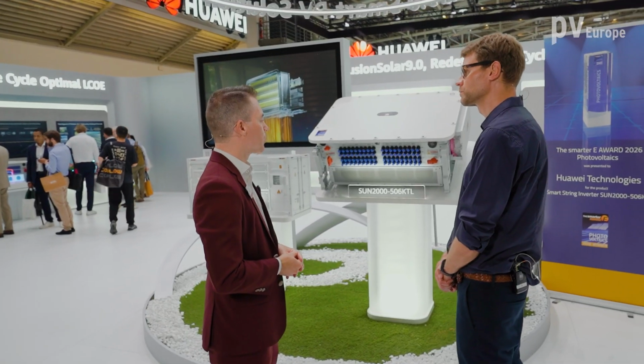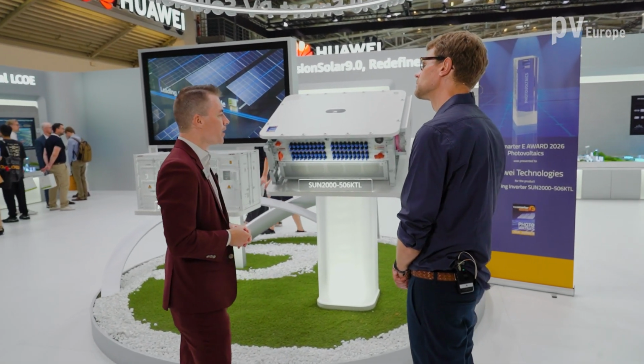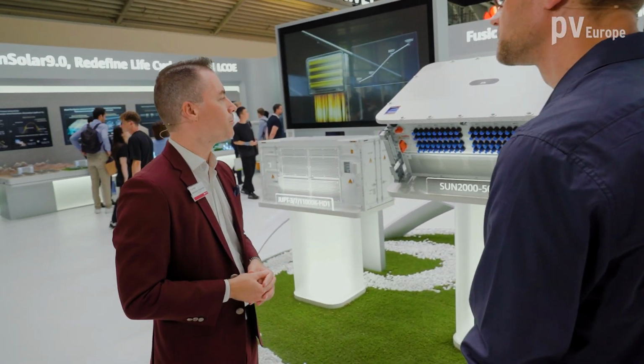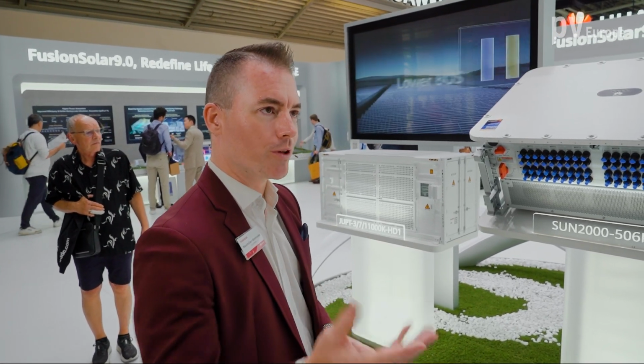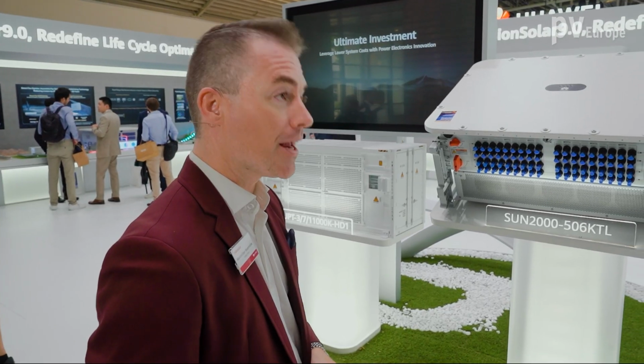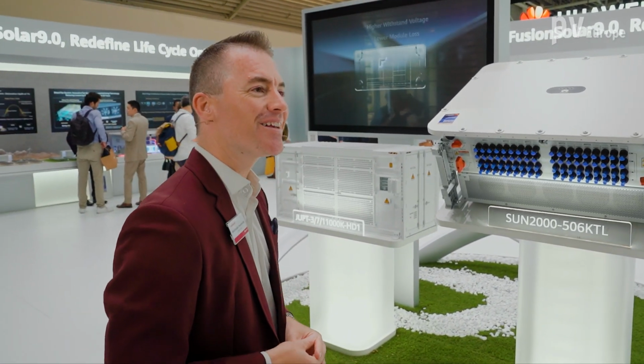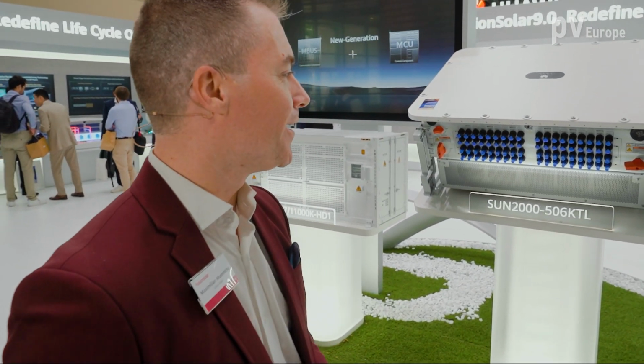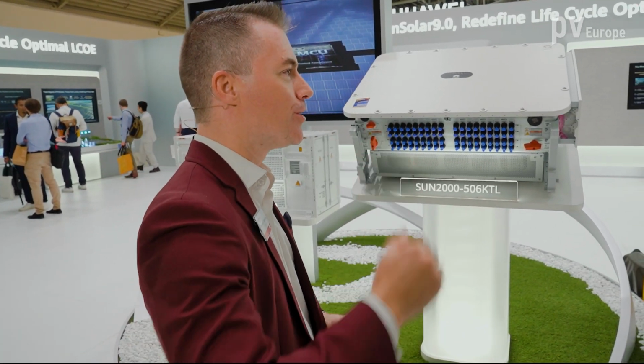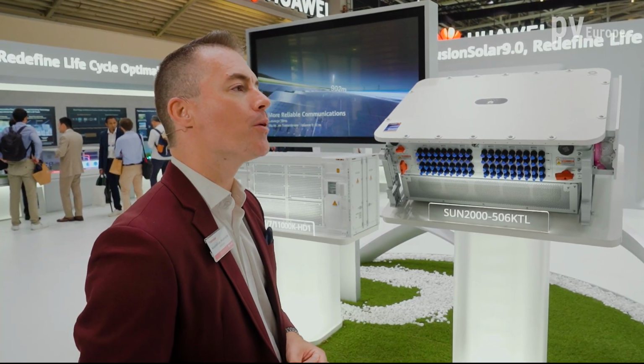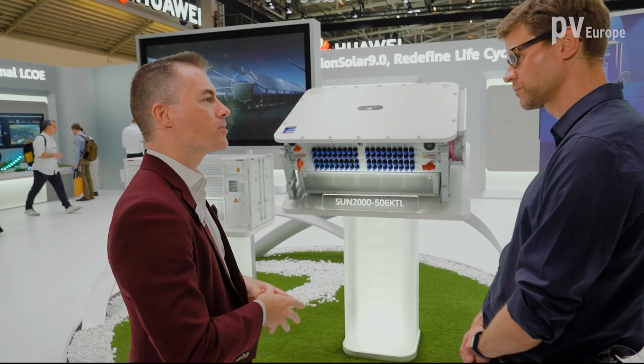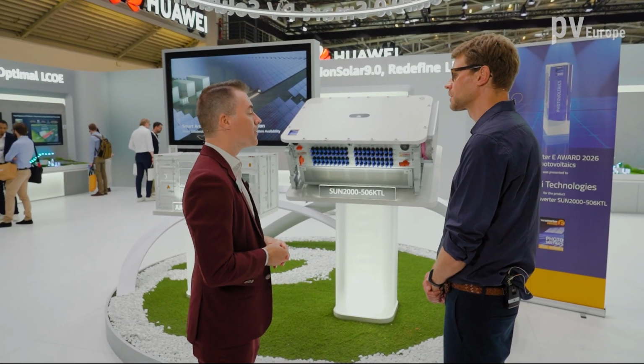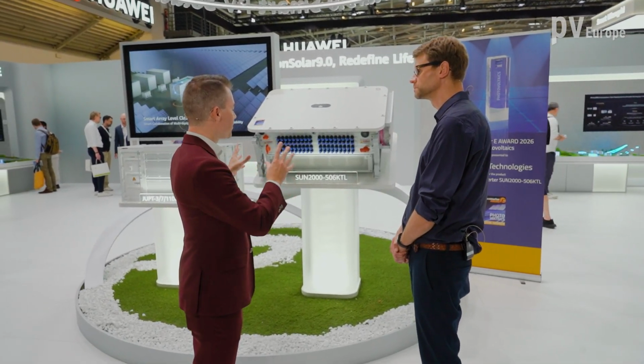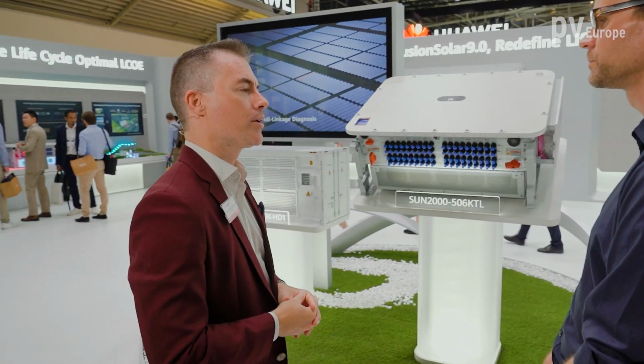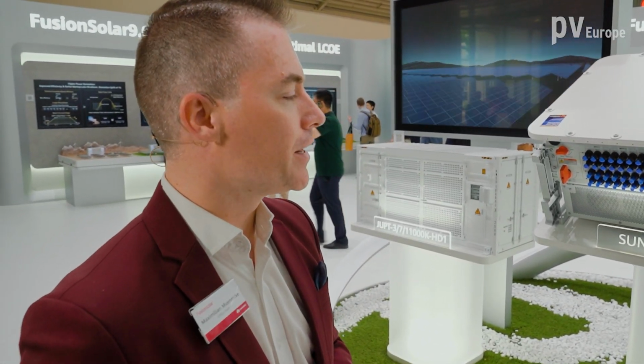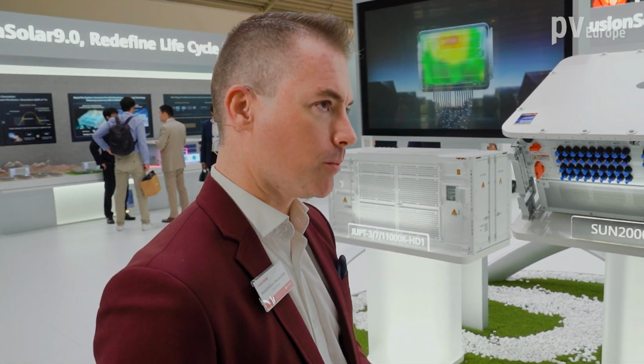Another very important step that we took in order to bring down the system size and weight is about 7 years ago we redefined the PV string inverter industry by going up with the AC voltage and the DC voltage to 800 volt AC. The industry thought it was a funny idea back then, but as we know by today, it was a good idea. The whole market followed us. Now we're going to the edge of what is possible in the low voltage side. We're going to 1000 volt AC. What does this mean? We're shrinking components, we're reducing the currents, and therefore we can reduce cable cross sections. And this system is therefore, with the balance of plants, if you compare it to the 330 KTL or its comparable 300 kilowatt design, we can bring down the balance of plant cost by about 20%.